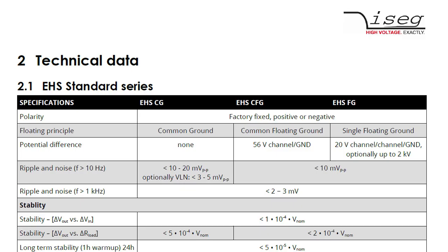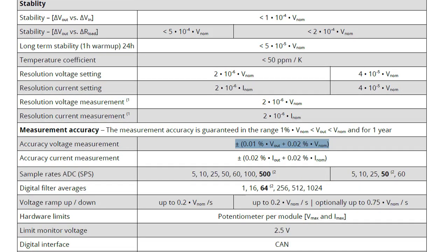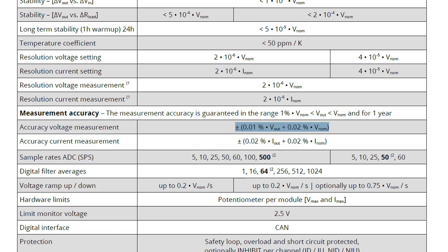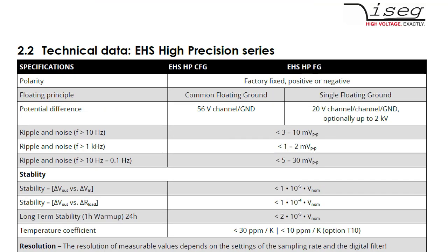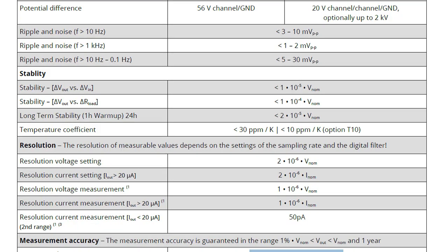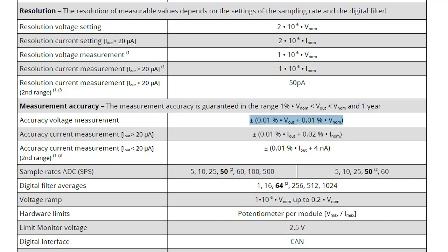Please check the datasheet of your Iseg module to find out the details about measurement accuracy. For standard precision modules, the maximum error is defined as plus minus 0.01% of V out plus 0.02% of V nominal. For high precision modules, the maximum error is defined as plus minus 0.01% of V out plus 0.01% of V nominal. This precision is guaranteed for the range from 1% to 100% of the nominal voltage.